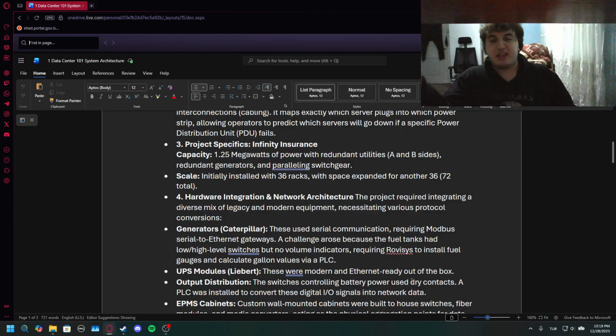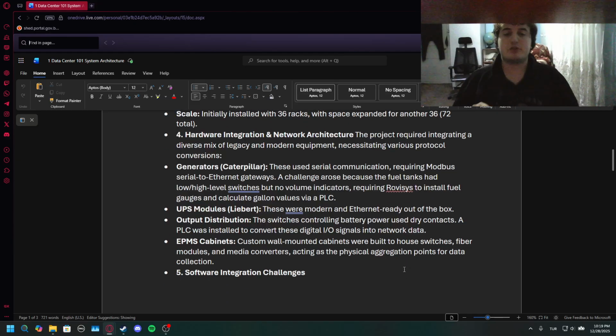They were saying how a PLC was used to turn these signals into network data that could be used inside the system, because we want an eSCADA, so obviously I/O signals alone will not do. So these switches control the battery power specifically, using dry contacts.